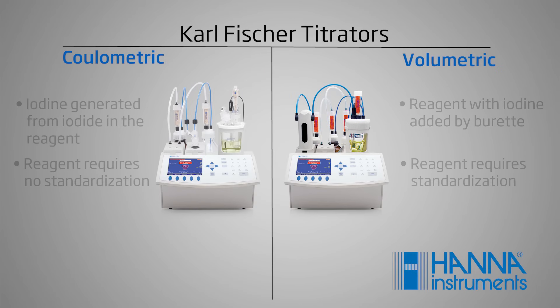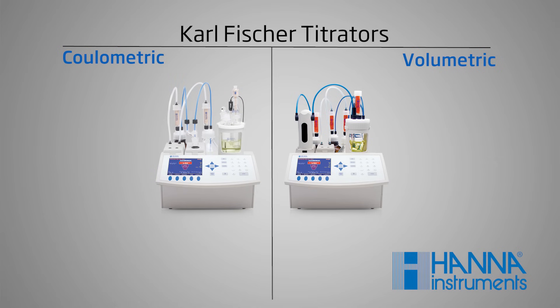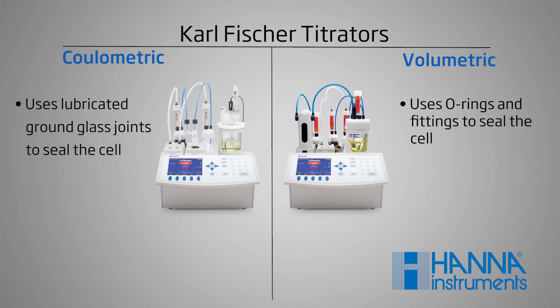Because of the way iodine is added, there are a few other differences. For example, volumetric and coulometric titrators use different reagents. Sometimes the different titrators will also have different methods for sealing the cell from the atmosphere. Coulometric models tend to require more tightly sealed vessels.